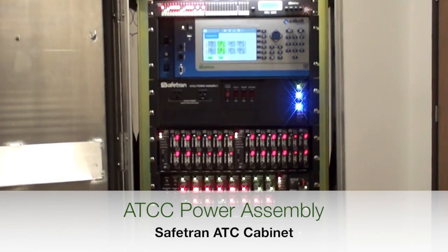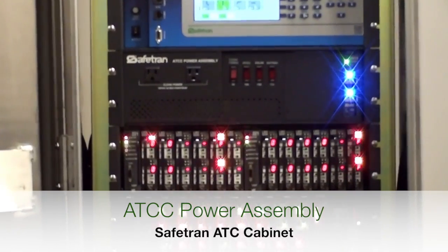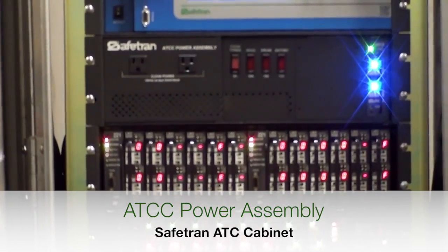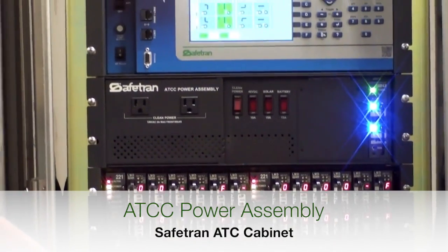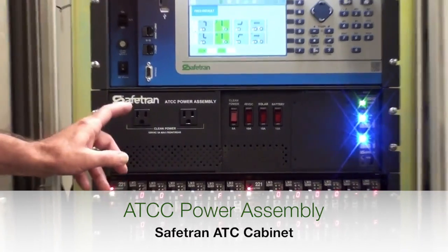Here is the power assembly. Notice the flasher is located in the power assembly. By locating the flasher in the power assembly, most of the other sub-assemblies in the cabinet can be removed while maintaining the intersection in a safe flash mode.